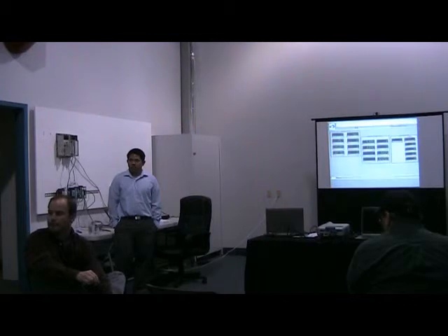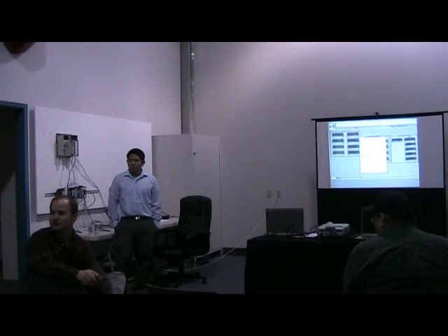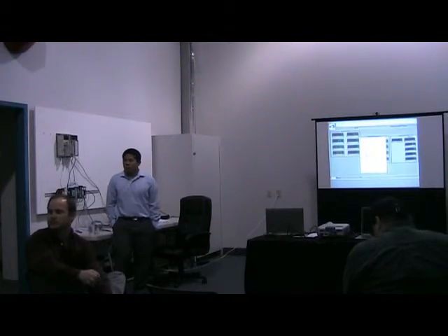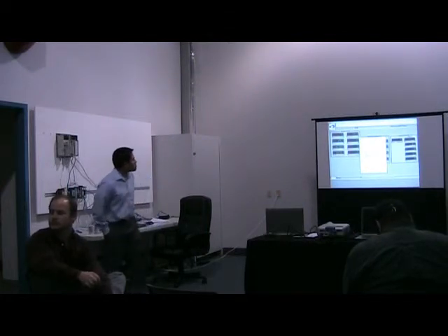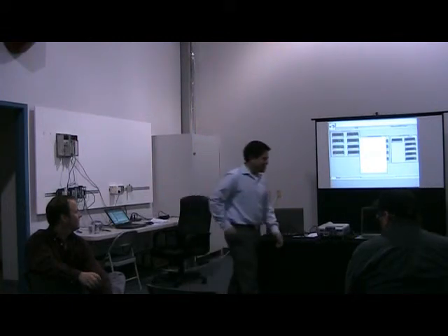So we had to go back through all our instruments, and we had to tell the guys, look, you can't be doing this no more. You've got to go 11 point calibration. And we bought Beamex calibrators that have the pressure and the current loops built into it, which automatically created a calibration. They couldn't fudge no more. They talked to them via HART, and they monitored.